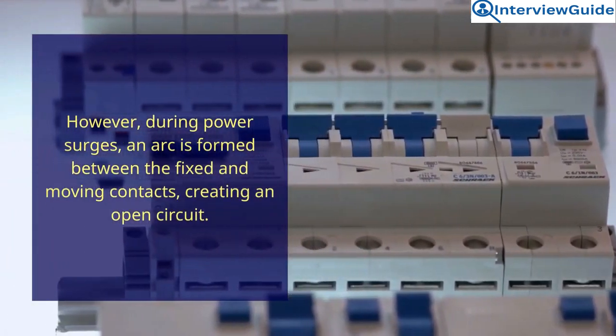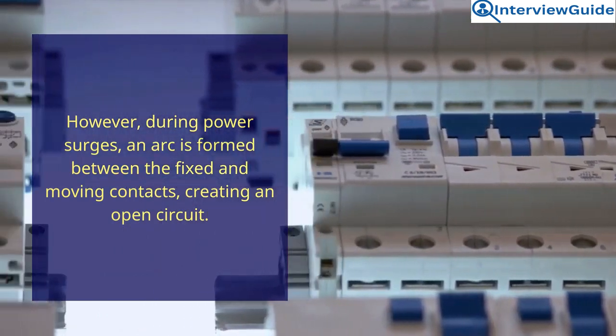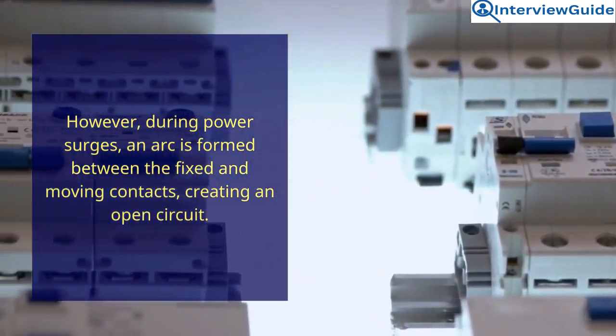It has fixed and moving contacts. When everything is okay, the moving and fixed contact form a closed contact, thus allowing the current flow. However, during power surges, an arc is formed between the fixed and moving contacts, creating an open circuit.